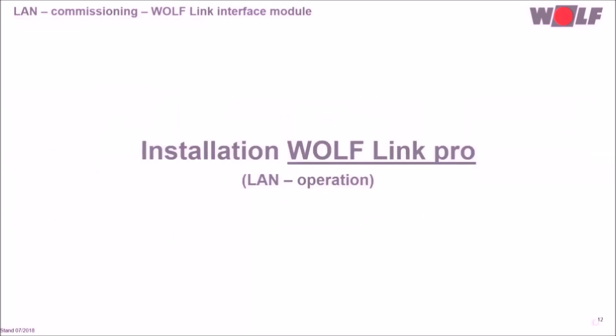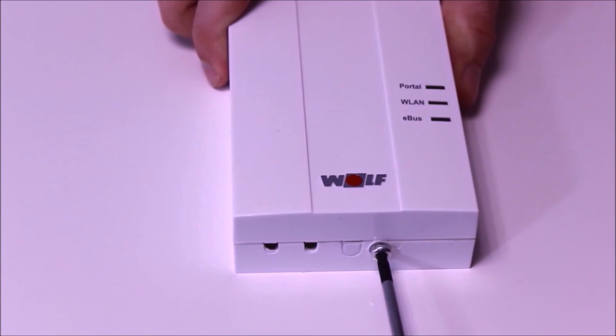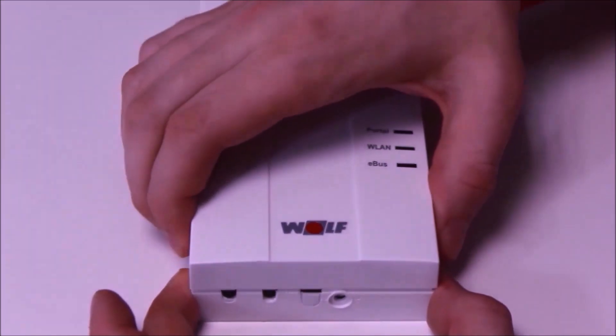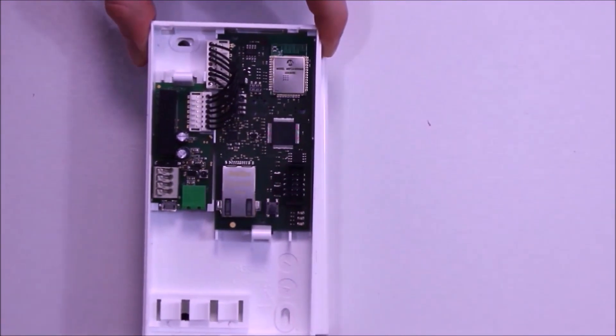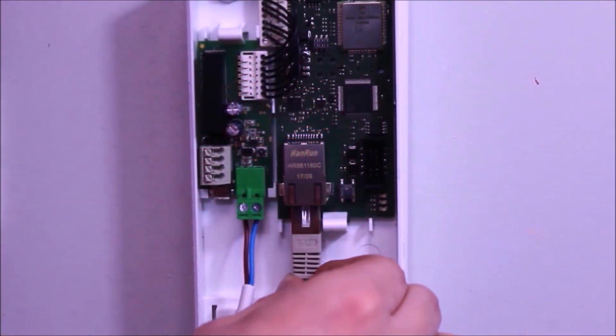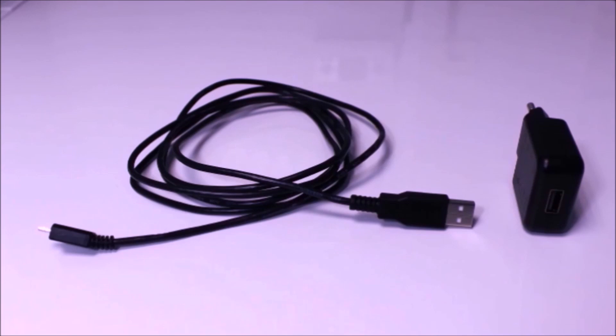Before starting the commissioning, let's look at the installation of the WolfLink Pro. First, we remove the torx screw at the casing, open the front cover, and install the WolfLink Pro at the wall. We establish the eBus connection between the module and heating unit, then connect the module and the router with the LAN cable. The module is supplied via a USB cable and the corresponding AC adapter. Now we close the casing — the module is installed.